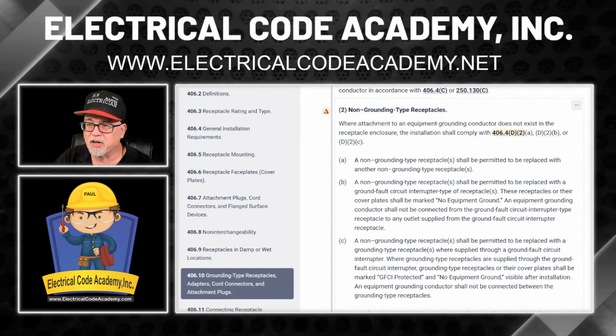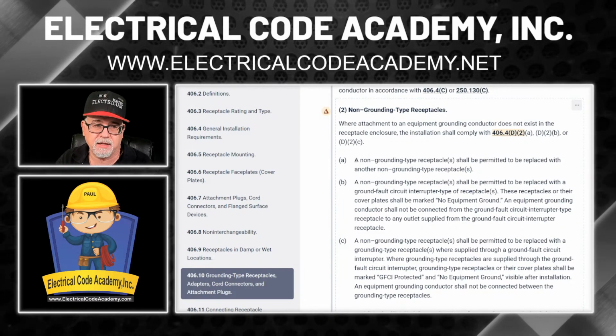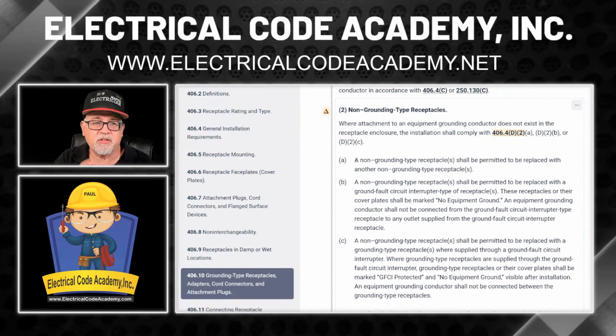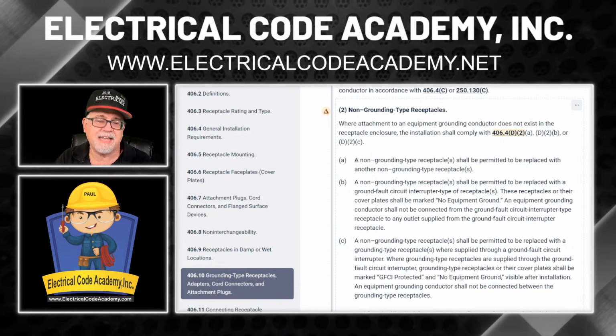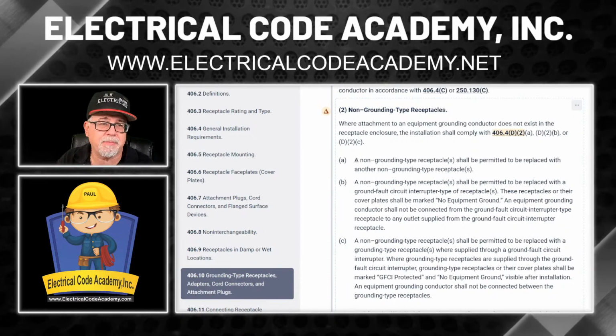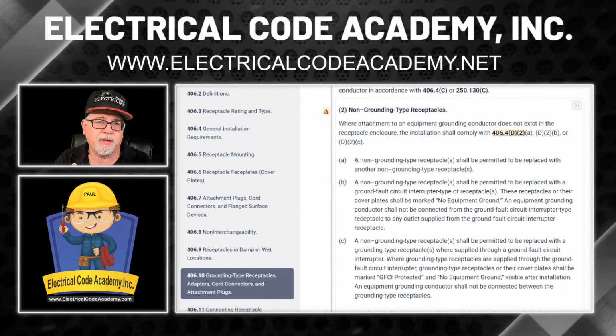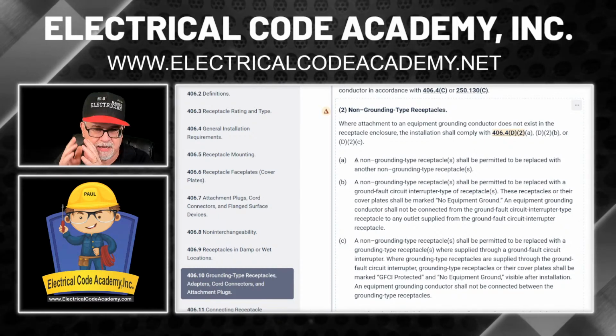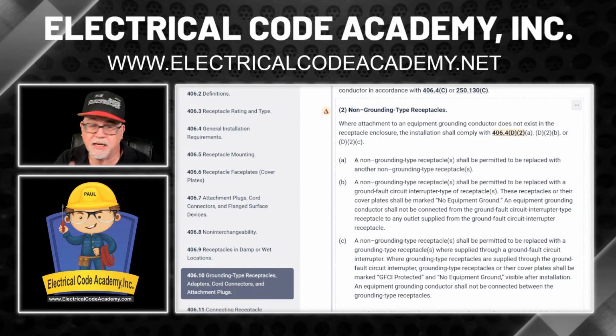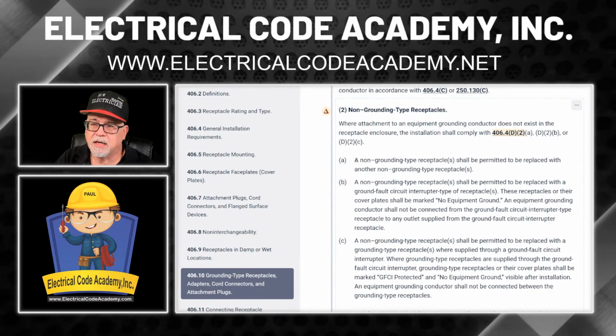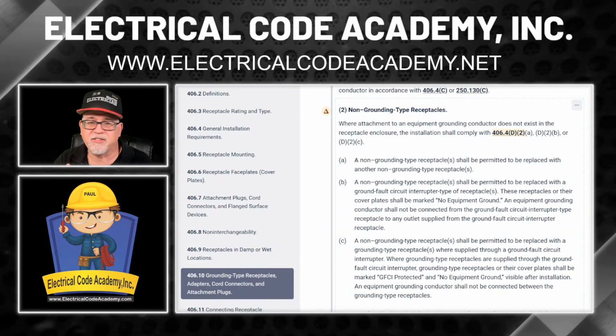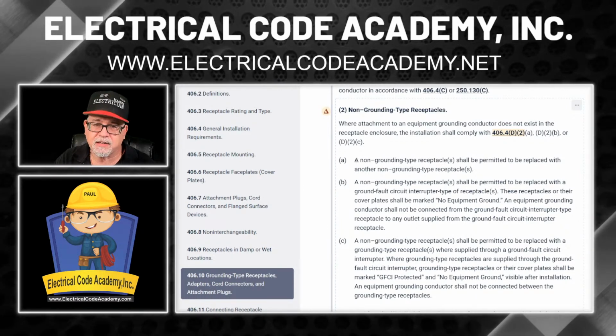No, you're not going to be using the equipment ground into it, okay? You want to make sure that you don't connect anything at this point to anything that might be going downstream of this receptacle, this GFCI receptacle, if you're using it in this fashion, okay? And it tells you that point blank. Obviously, the GFCI is not establishing an effective ground fault current path.